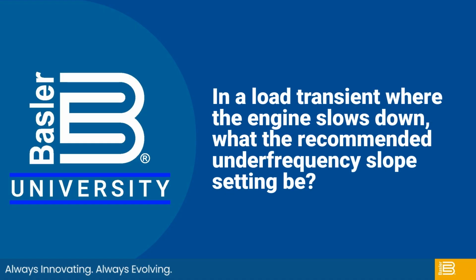In a load transient where the engine slows down, what would be the recommended under frequency slope setting? The slope setting itself for the under frequency limiter generally is left at 1.0, but if you need a more aggressive ramp reduction in voltage, then you can set it at a higher level. For example, a slope setting of 2.0 will reduce the voltage at twice the rate of frequency. So if your frequency drops 10%, your voltage will be reduced 20%.